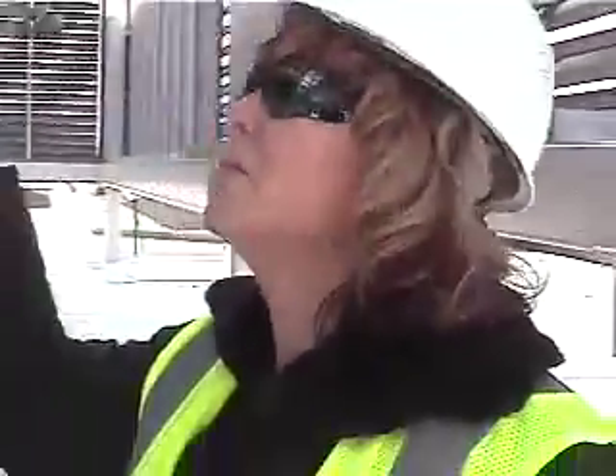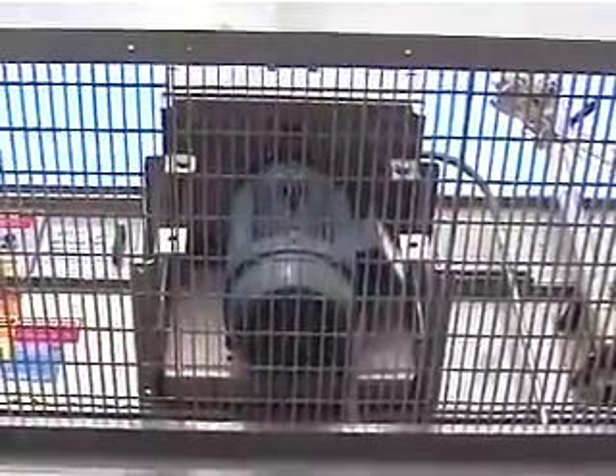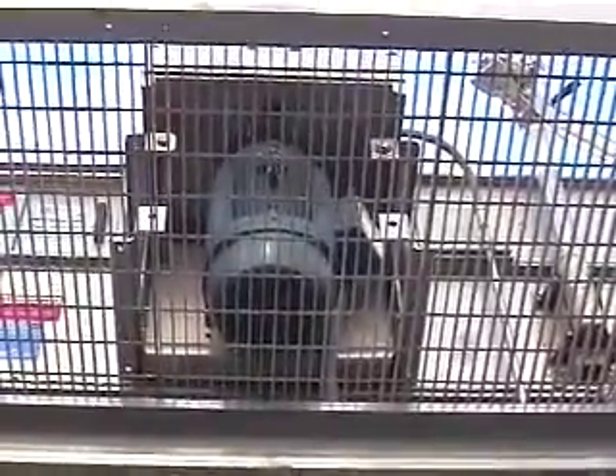And the rest of the cooling tower motor and equipment is up there. So that's the motor, fan motor. Right here is where you adjust the tensioning for the belt. Above that is the cover. There's a cover right there. And then the belts in there. There's a little guard that you would have to remove once the tower's locked out. But while it's operating, of course, you're going to have this on there.